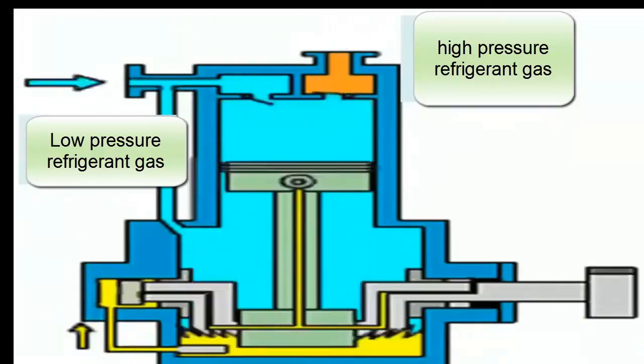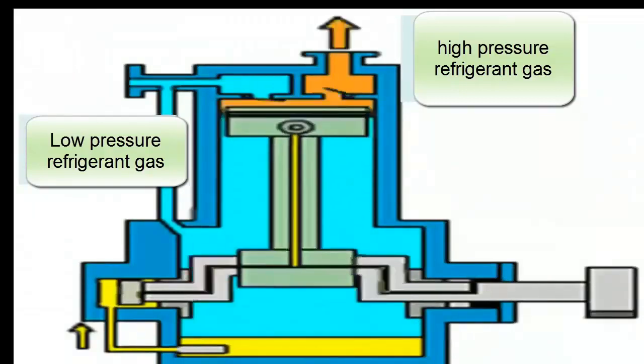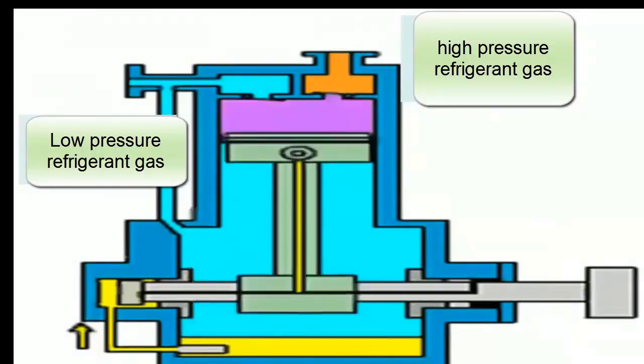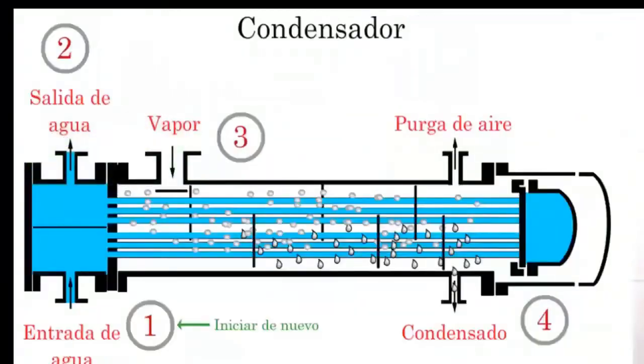Condensation is going from the vapor state to the liquid state. Once compression is done, we pass the refrigerant through the condenser, where with high pressure and a cooling that the refrigerant undergoes, the passage from vapor to liquid occurs. So the condenser requires two fundamental things: high pressure and also cooling.